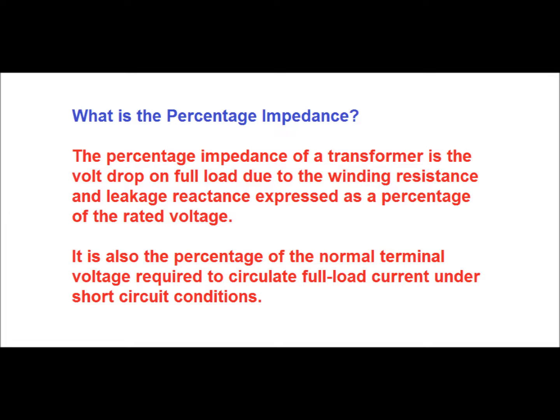For a power transformer, if the primary is short circuited, then you have to give that percentage of the secondary voltage to circulate the full load current in the primary side. Alternatively, if the secondary is short circuited, you have to give that percentage of primary voltage to circulate full load current in the secondary side.